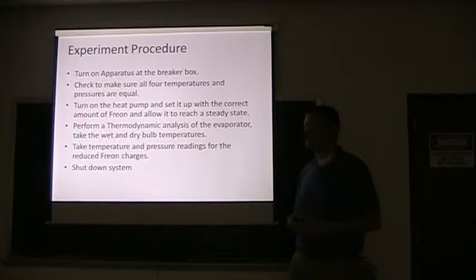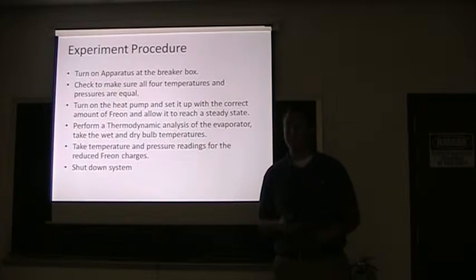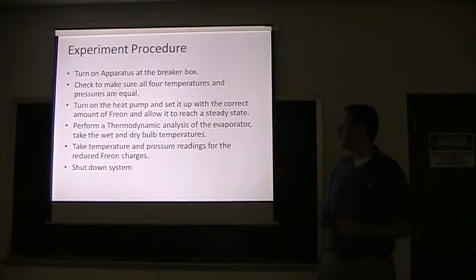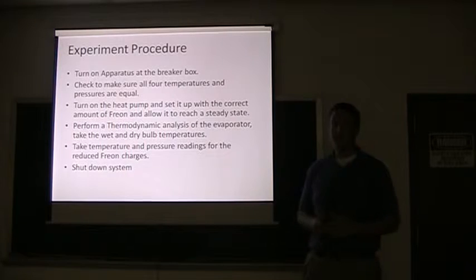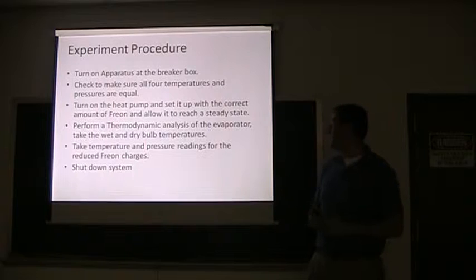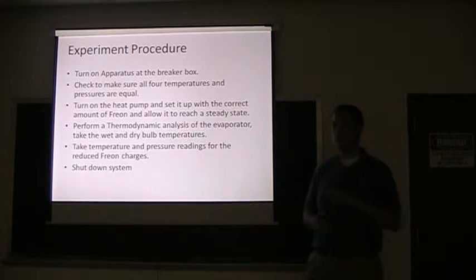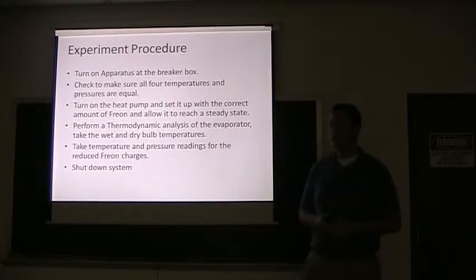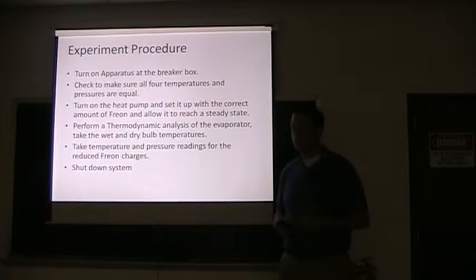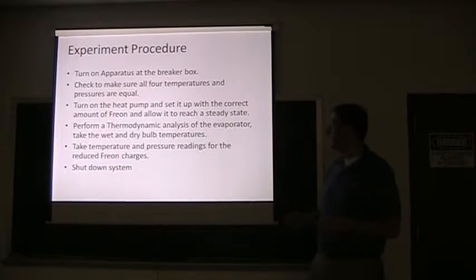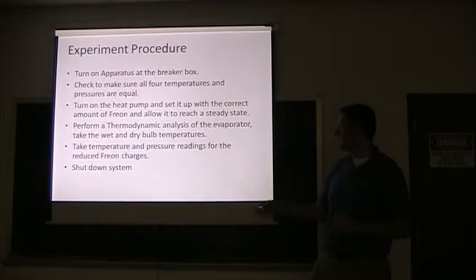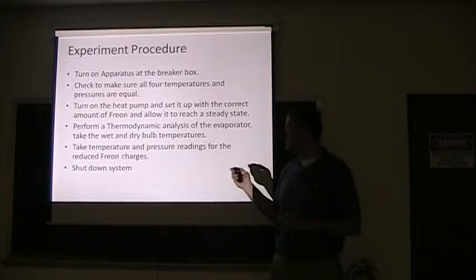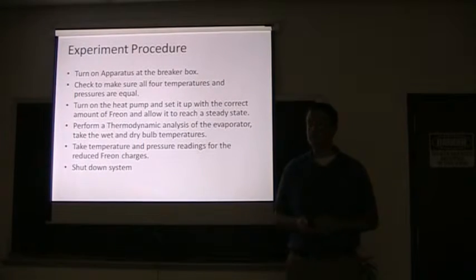The procedure of our experiment is for us to turn it on at the breaker box. We'll then check to make sure all four temperatures and pressures are equal, hopefully at room temperature. If they're not equal, we'll need to go through calibration, which is in the lab manual. We'll turn on the heat pump and set it up with the correct amount of Freon, which I was talking about the charge level, and allow it to reach a steady state. Through the thermodynamic analysis of the evaporator, take temperature and pressure readings from the Freon charges, and then we need to make sure we shut down the system safely.